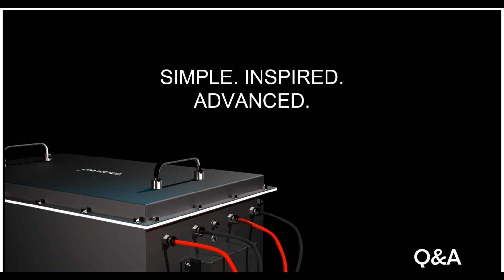There are a couple of things that determine how you design your battery for a particular application. One is the total number of units required as backup. For example, if the total load is 10 kilowatt in a household and you require that load to run for about 4 hours, that means you require a total usable backup of about 40 kilowatt hour or 40 units. So that's one number you need to arrive at.